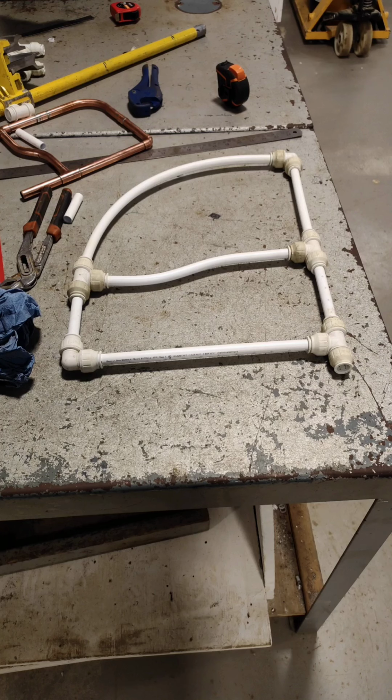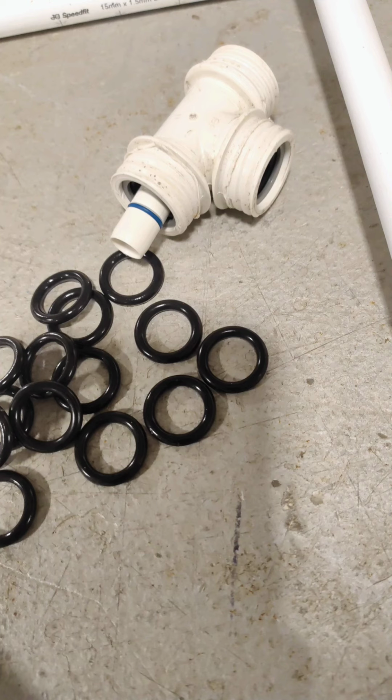It must be installed at a minimum depth of 750 millimeters and a maximum depth of 1,350 millimeters. It must terminate within the building with a screw-down type stop valve manufactured to BS 1010.